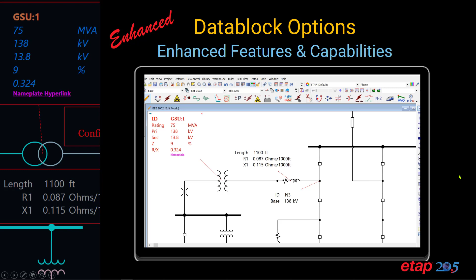Another capability we've added to ETAP is graphical device selection by type. Simply press the Shift key and right-click on any device, and the program automatically selects all devices of the same type, allowing you to make common or bulk actions such as changing the size, font style, or bus thickness. It's a very quick and effective way of changing all devices of the same type without graphically selecting each one individually.